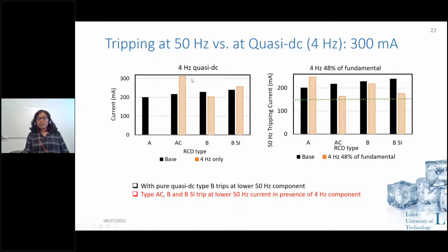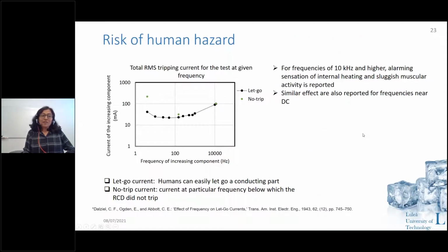Type AC RCDs tripped, but they required, of course, higher current. And in this case also, it is a different behavior. Type B RCDs also tripped with the 4 hertz component, and in fact they required slightly lower fundamental current in type B RCDs. But a general conclusion we could not reach for type B RCDs, because we have only two type B RCDs. Yeah, so considering all this, what is the risk of human hazard at higher frequencies?